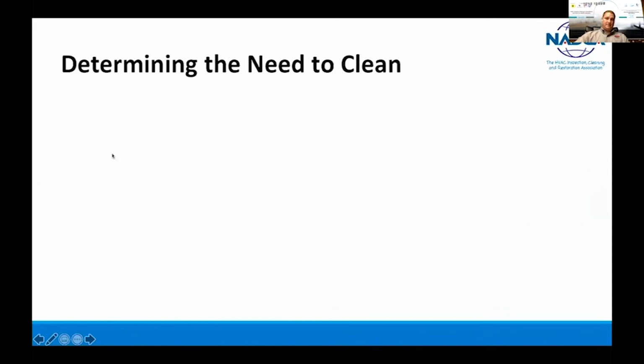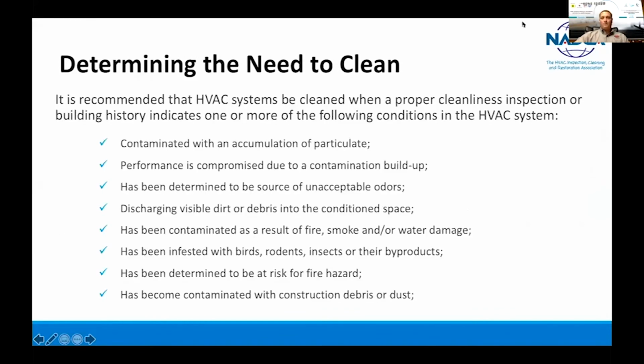It is recommended that the HVAC systems be cleaned when a proper cleanliness inspection or building history indicates one or more of the following conditions in the HVAC system: contaminated with an accumulation of particulate, performance is compromised due to a contamination buildup, it has been determined to be a source of unacceptable odors, discharging visible dirt or debris into the conditioned space, has been contaminated as a result of fire, smoke, and or water damage, has been infested with birds, rodents, insects, or their byproducts, has been determined to be at risk for a fire hazard, has become contaminated with construction debris or dust.